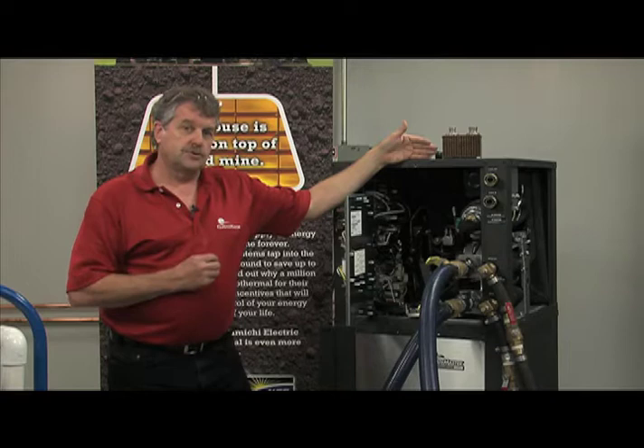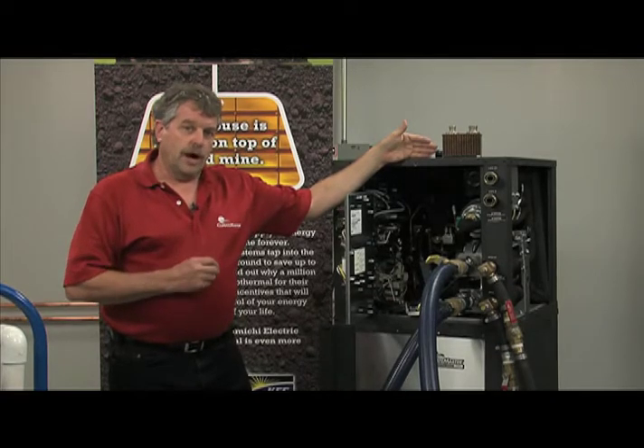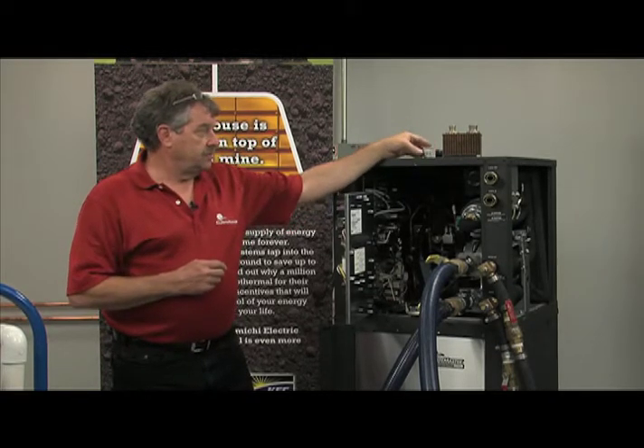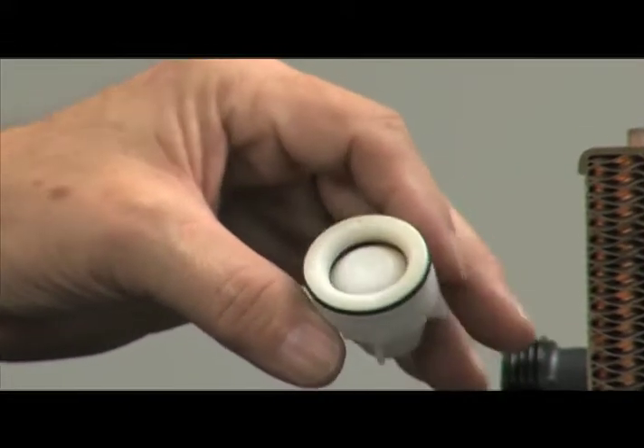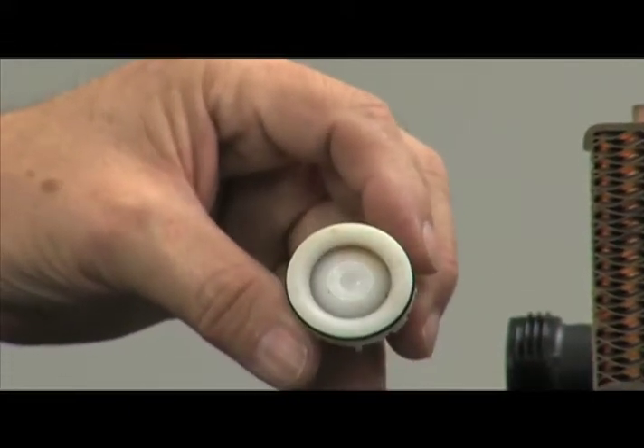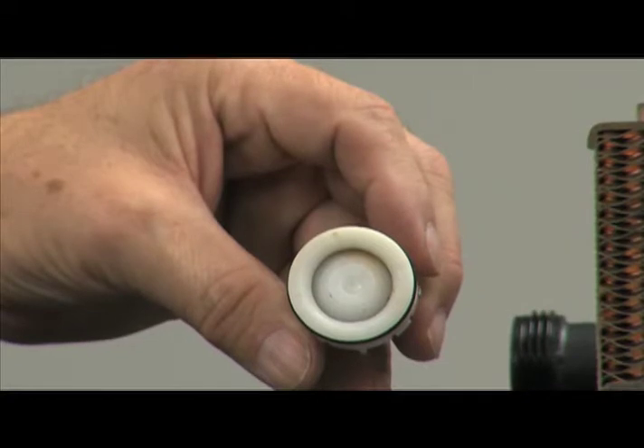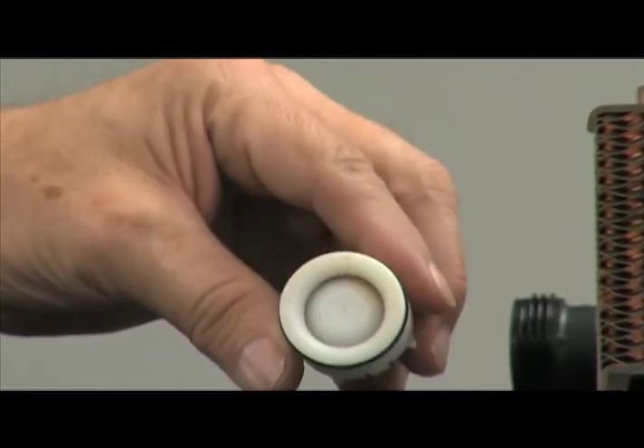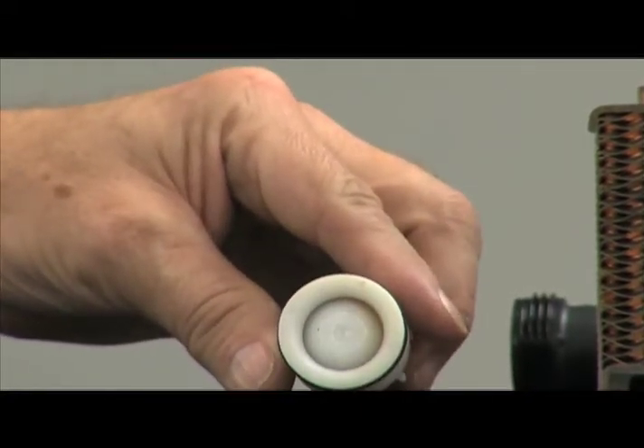The other component that's throughout our vFlow iGate Connect with the EXM board is going to be internal pumping with check valves. It's a spring check valve. It's in the volute of both the hot water as well as the loop pump. So follow proper procedures to make sure you don't compromise those so that they get stuck and hang open.